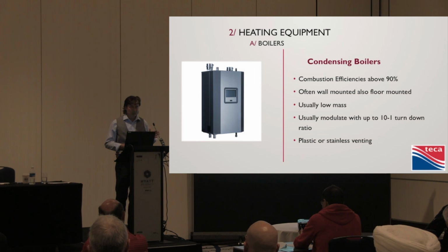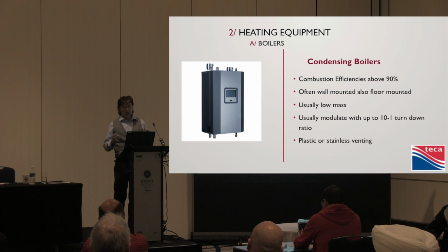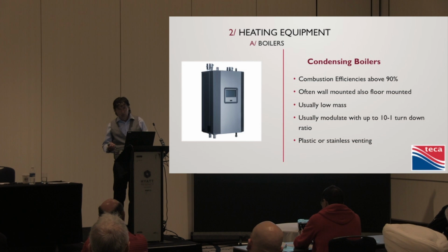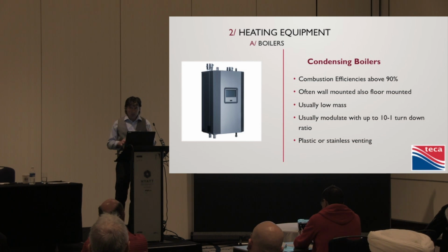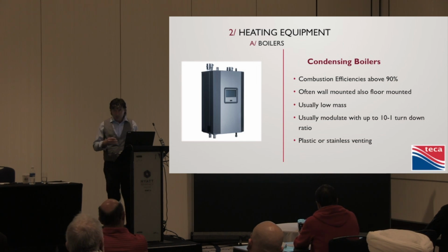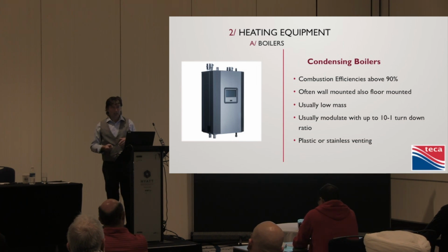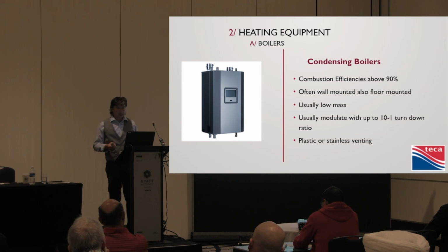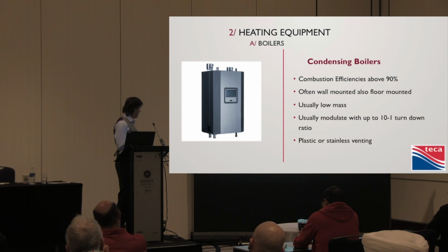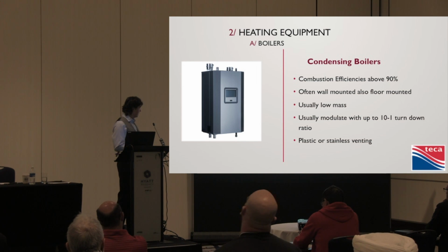But for anything residential, you can get up to 399,000 BTUs in a condensing wall-mounted boiler. Why 399? Why not 400? At 400, there's a different classification as per the gas code. At 400,000 BTUs, now you need an A ticket; it's not your average B ticket that can work on that boiler. It's got a power burner, and the code says 400,000 or over, thou shalt have an A ticket. There's a handful of guys in BC that have an A ticket. Most gas fitters are B tickets. So why not make 399,000 the largest? These go anywhere from 50,000 to 399,000 in a wall-mounted version like this.